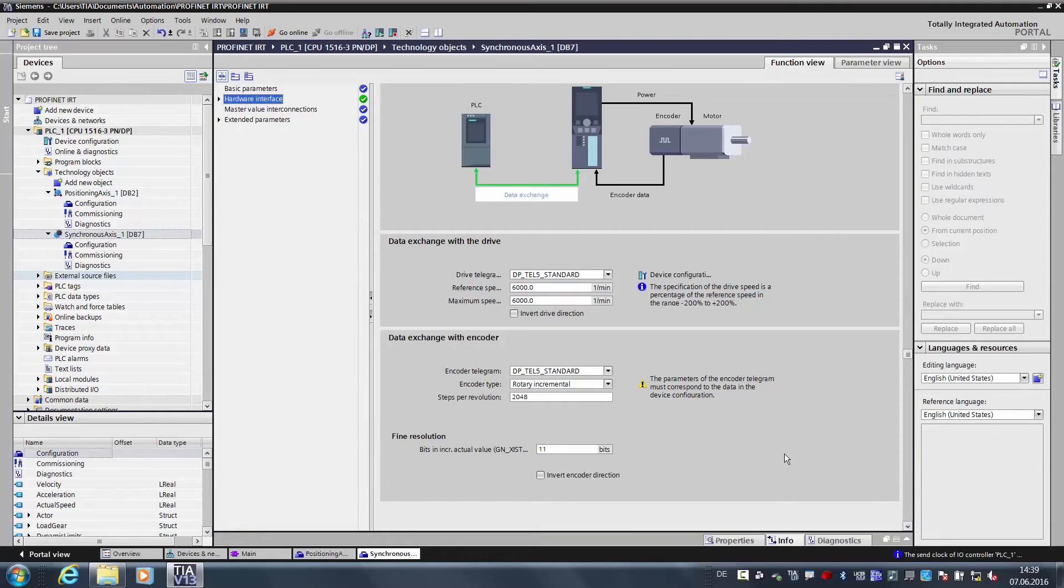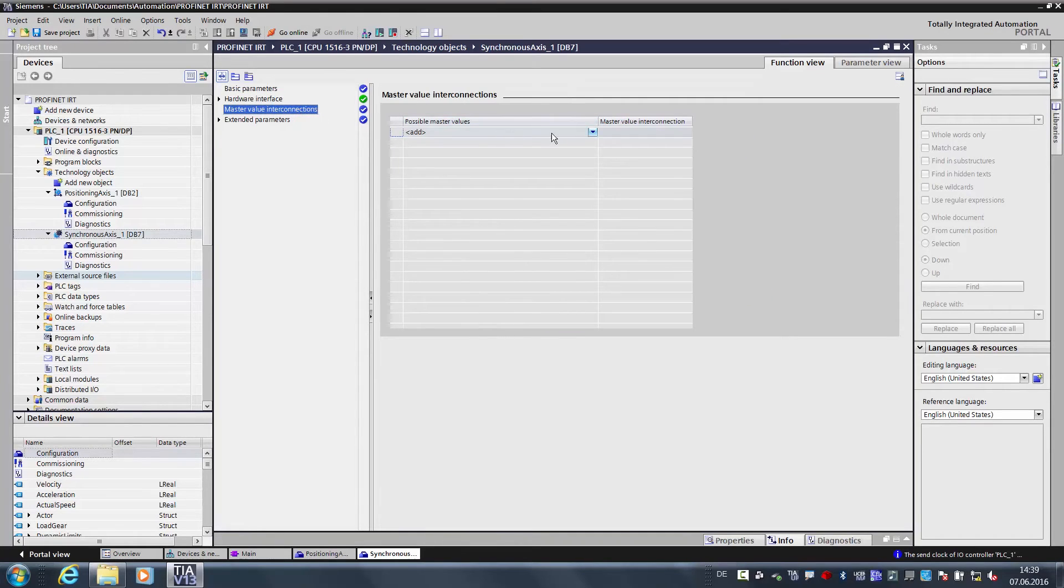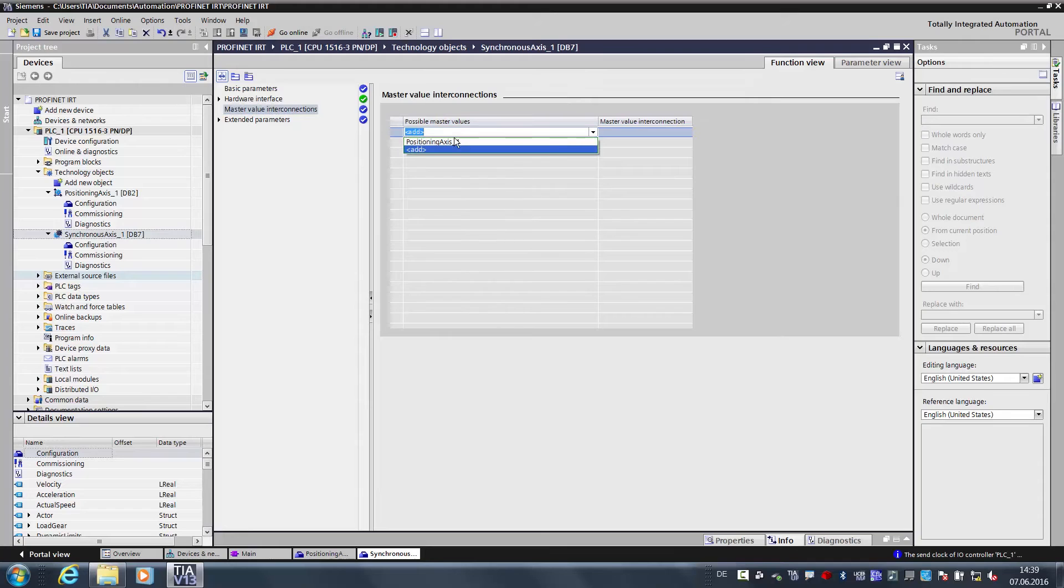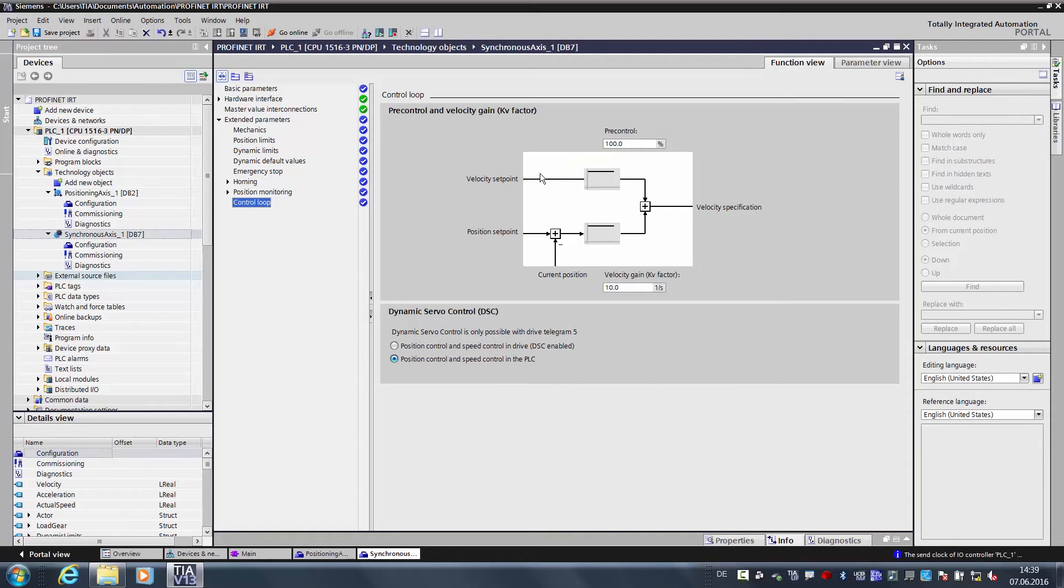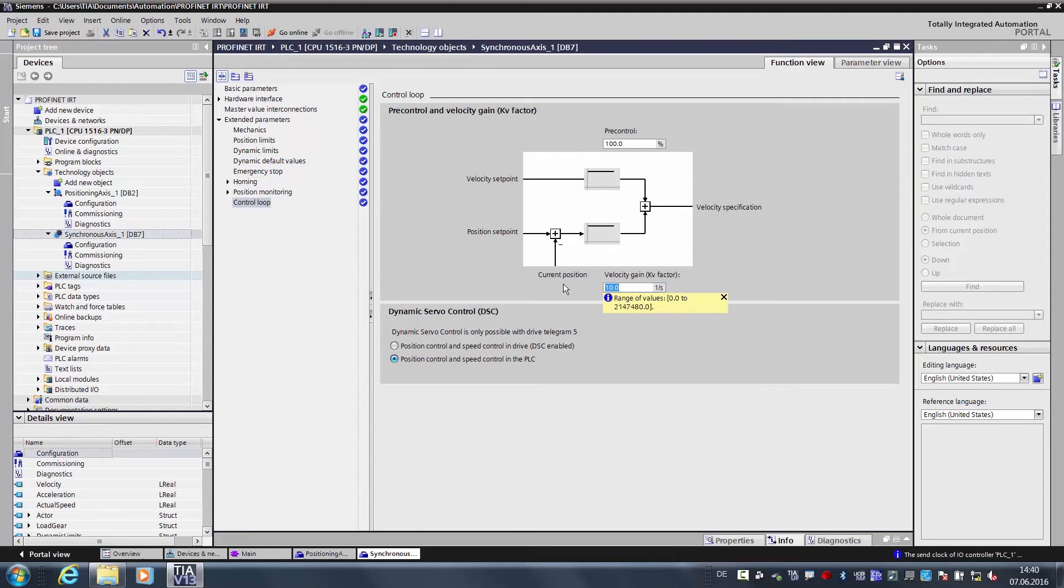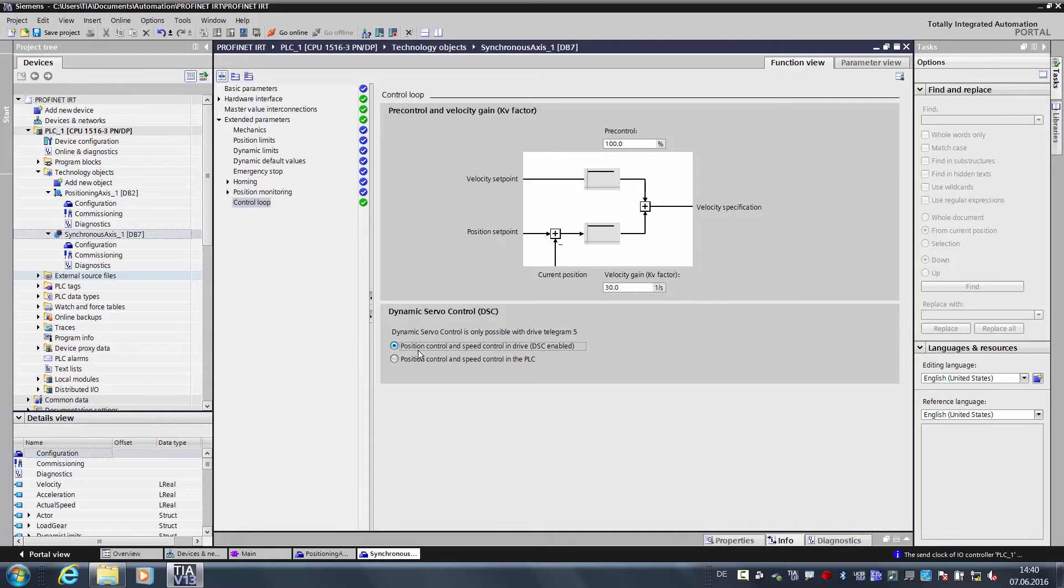Now we want to specify the master for the synchronous axis. Here we select the positioning axis. And now we still have to edit the advanced parameters, as with the master axis. And here we keep the pre-control of the controller at 100%, increase the KV factor from 10 to 30, and we also activate the DSC.